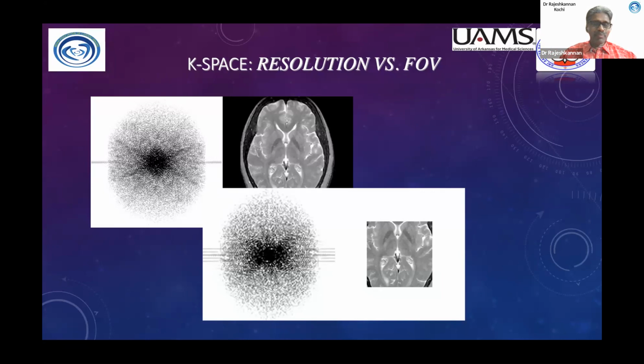But if we can keep adjusting the number of segments with a scan time of no more than 10 to 12 seconds, because most persons can hold their breath for about 10 to 12 seconds, so if each image is acquired within 10 to 12 seconds, then you always get a more or less consistent temporal resolution. So that is one way of doing it.